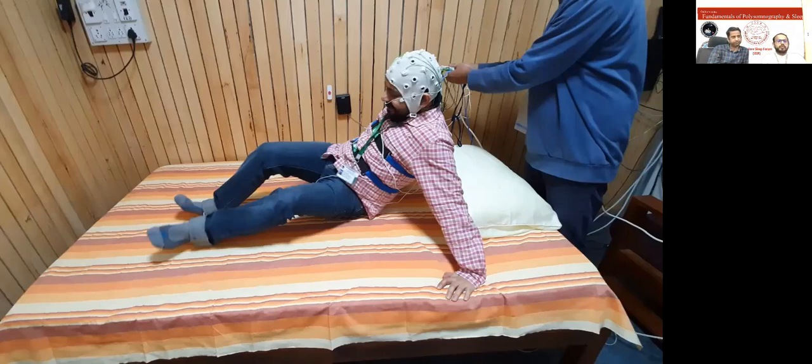When asleep, can the movement of the subject cause loosening of the electrodes? If yes, how is that addressed without disturbing the sleep? Good question. At times, when they move and squeeze on one side, some electrodes will go bad in those sections. But when they turn back, most of the time it will go well.